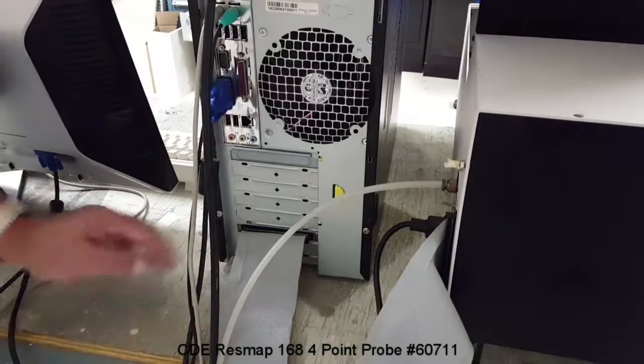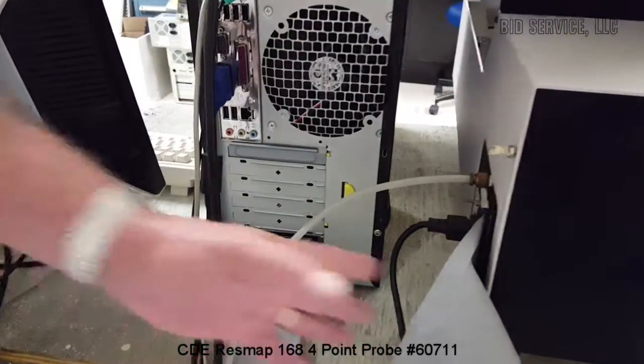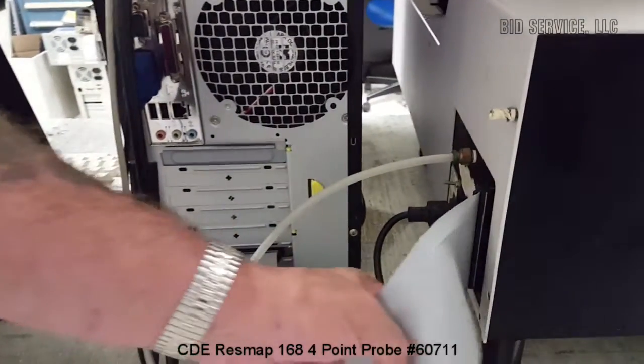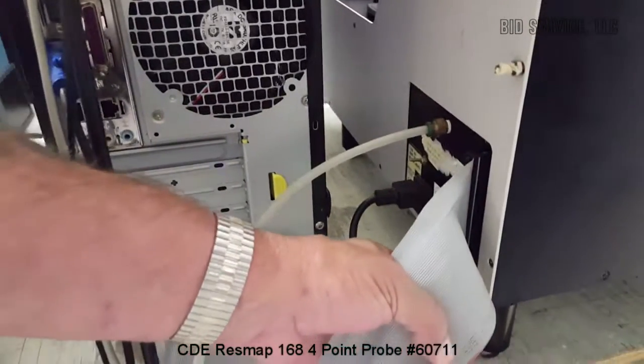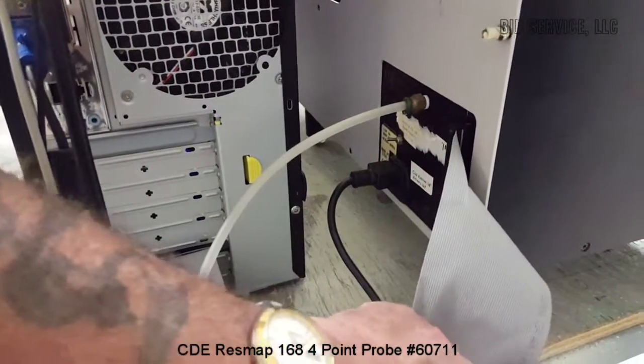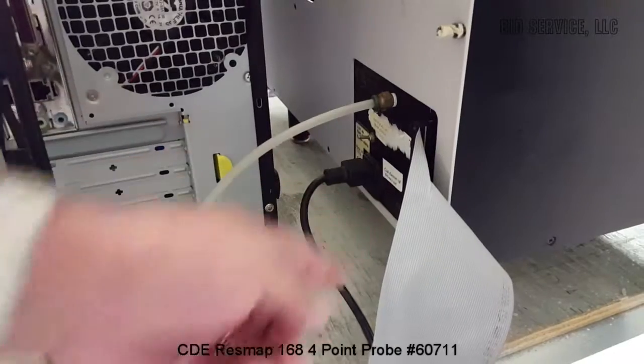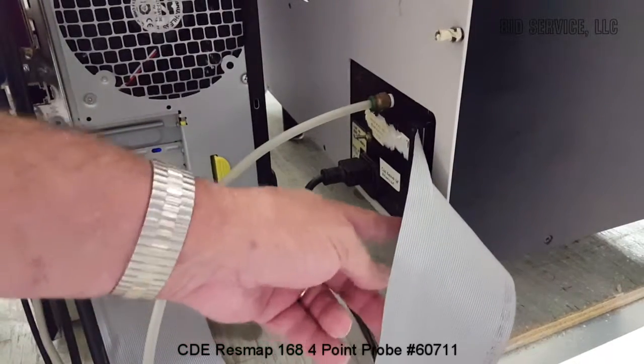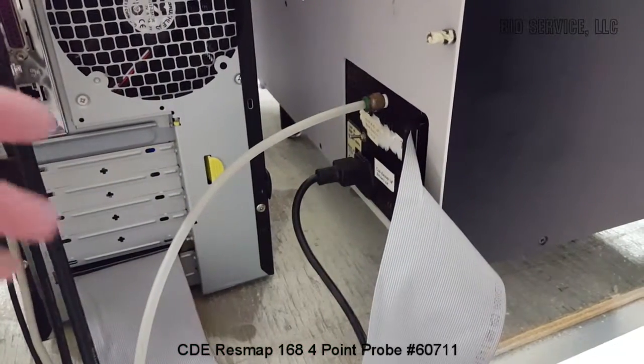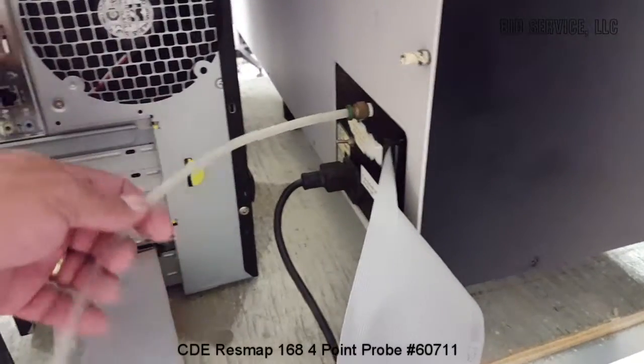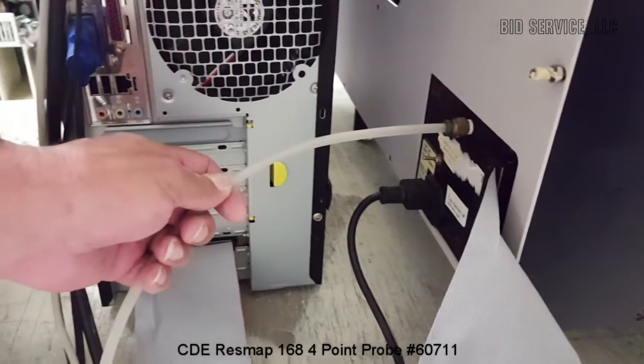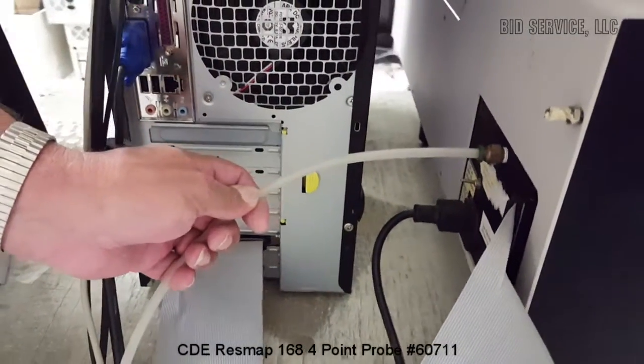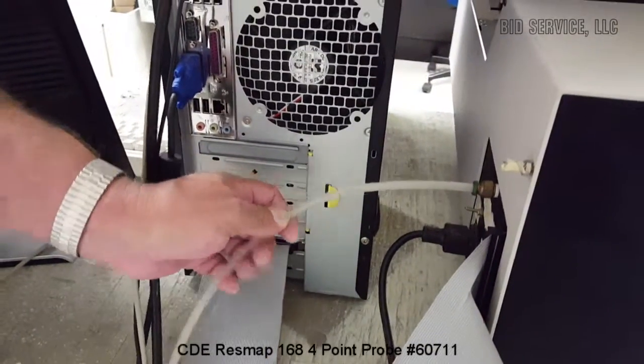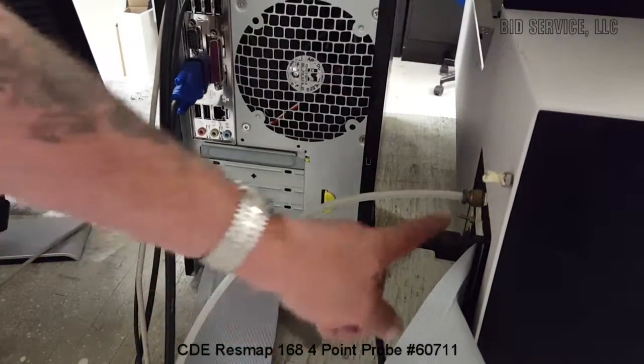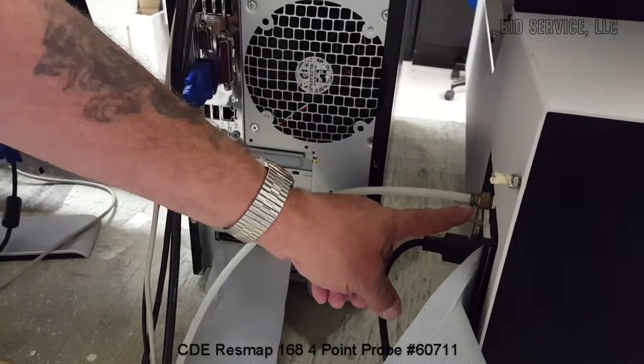You have a ribbon cable that connects the computer to the system here. You'll notice that the ribbon cable has a red line on the bottom. And that red line needs to be at the bottom position on here. So you can see how the connection is made. Your vacuum connection is here. This unit does require a vacuum pump, but does not come with one. And it's 115 volts, and your power switch for this unit is right here.